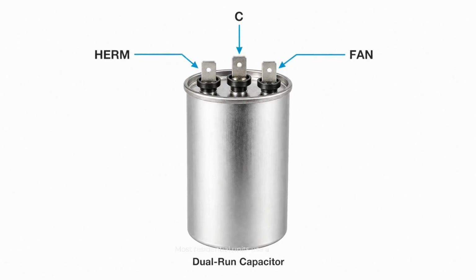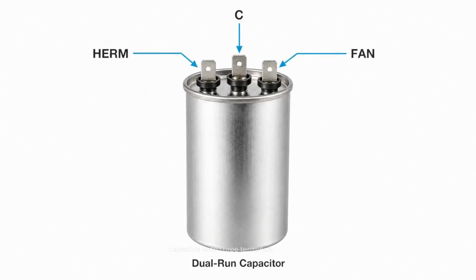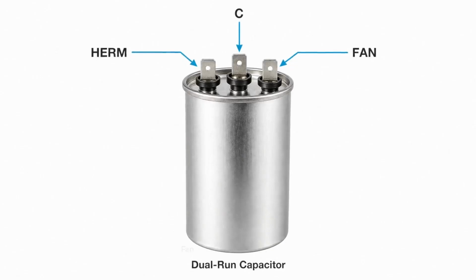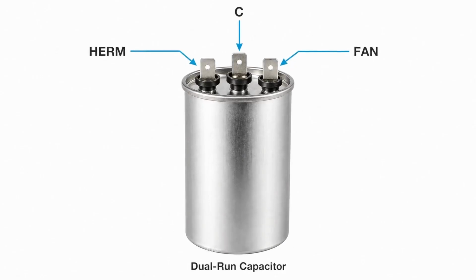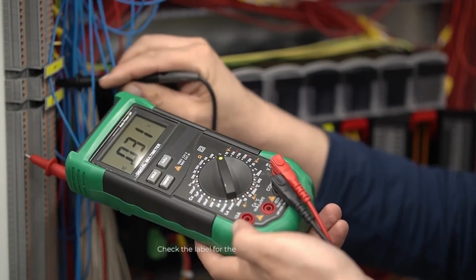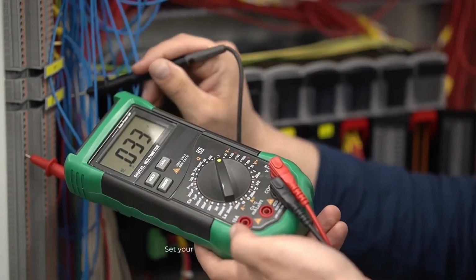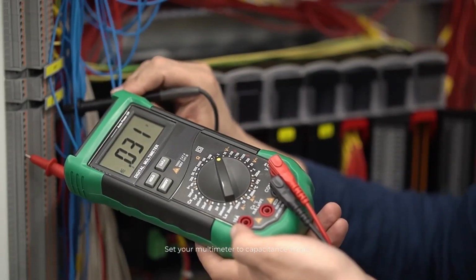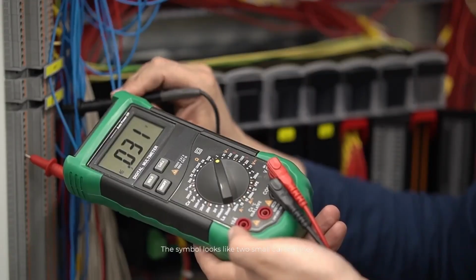Most residential units use a dual-run capacitor with 3 terminals. HERM for the compressor, fan for the condenser fan motor, and C for common. Check the label for the rated MFD and voltage. Set your multimeter to capacitance mode. The symbol looks like 2 small curved lines.